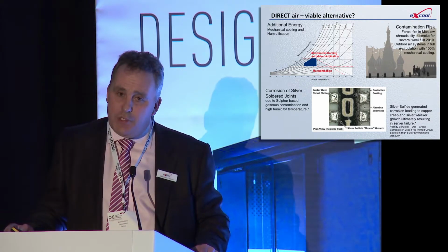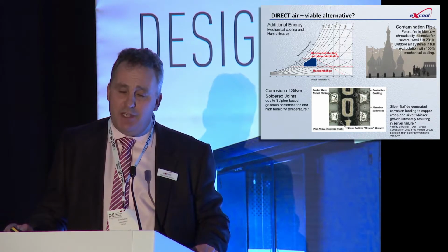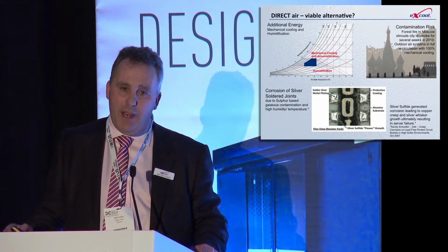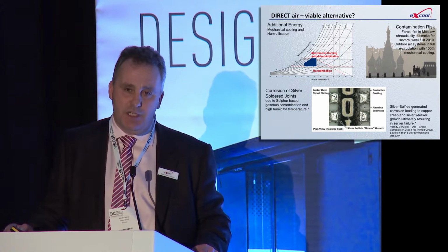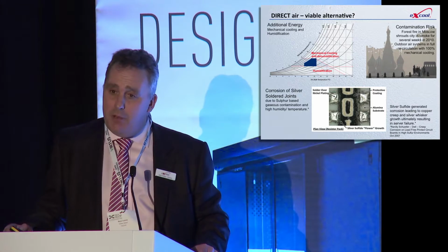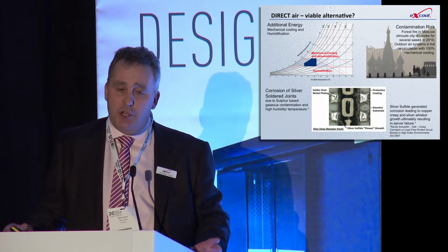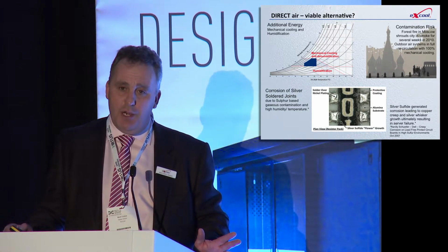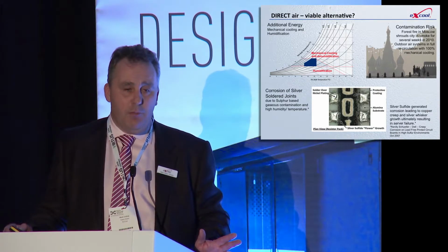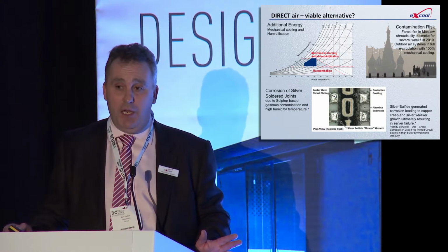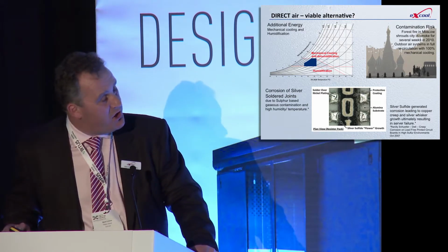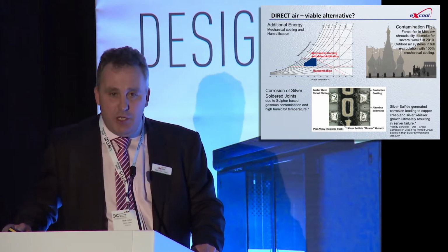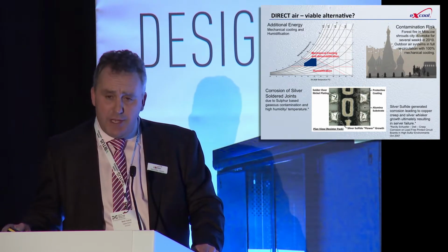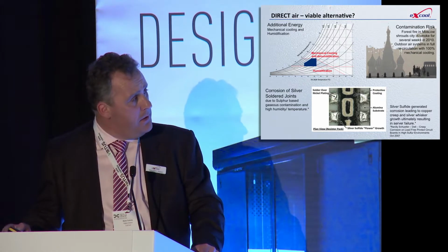But more importantly, it's the winter operation. Humidity drops rather dramatically if you're bringing outdoor air in during winter, particularly in the middle of winter when it's below zero outside. So you need to introduce moisture into that outdoor air stream, and that's normally done with electrode boiler humidifiers. So you're basically boiling big kettles to introduce steam into the data center to maintain humidity. So huge amounts of energy are required to do that.